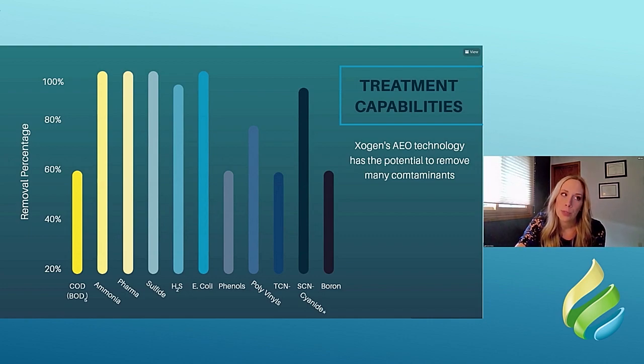And then often what we'll see is about a 40 to 60, around 50% BOD or COD reduction. So we do not, with this process, get rid of all of the organics. So it's a good complementary process to, say, a simpler lagoon, a flow through system where you're getting good BOD removal, but perhaps you're struggling to nitrify during the winter time. But I won't belabor that too much. We can get into the actual numbers.